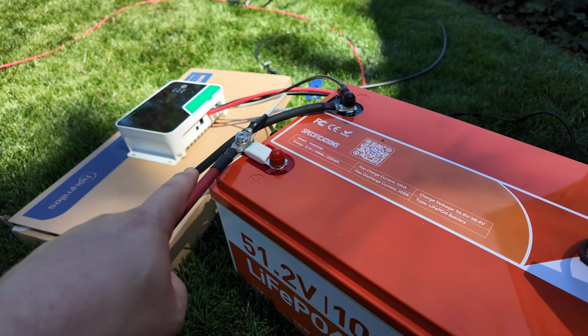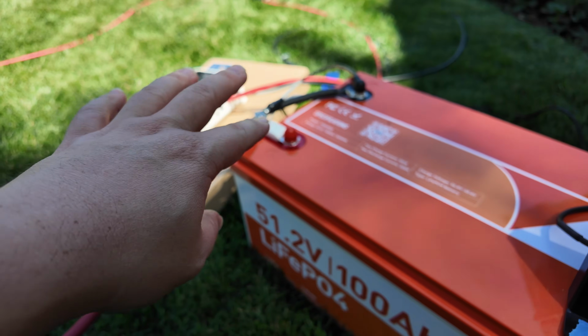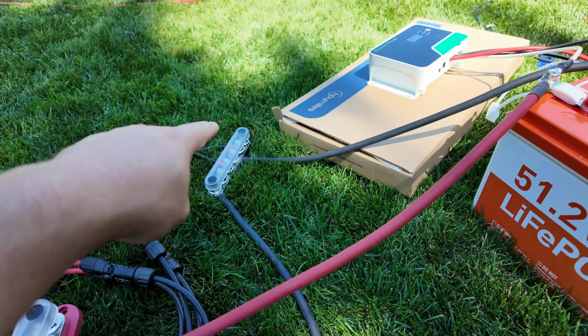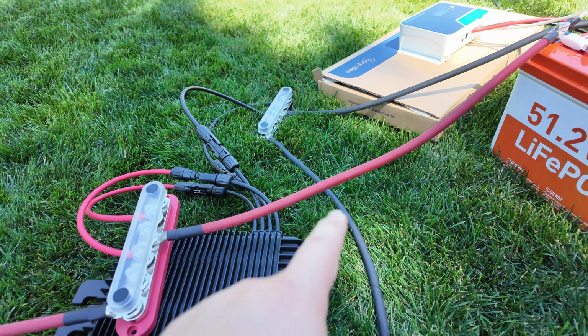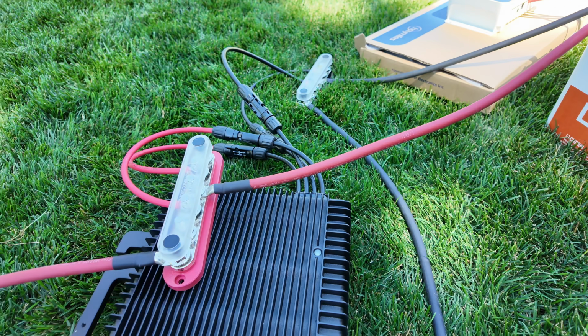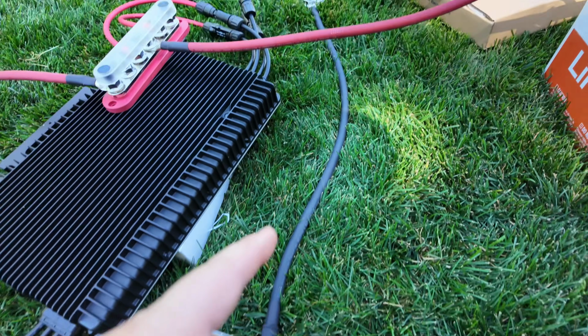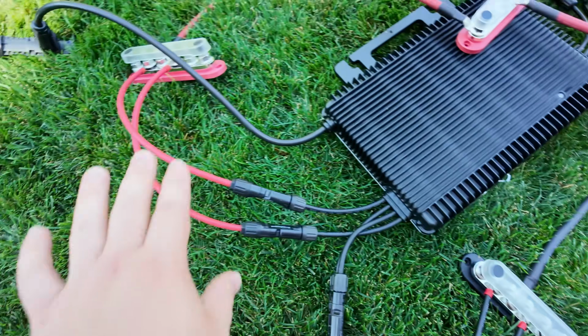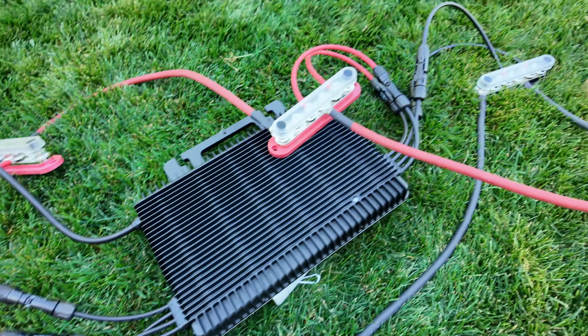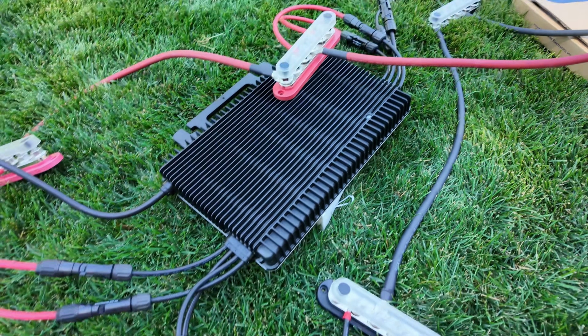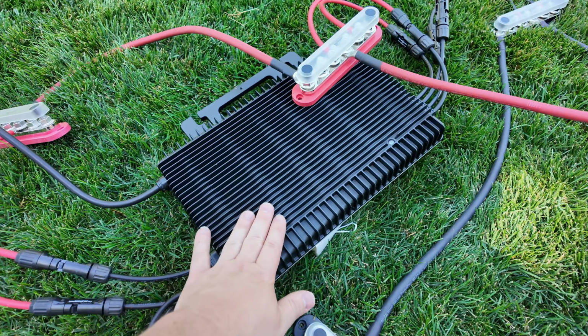I've got a fuse coming off the battery, positive and negative. The negative feeds one bus bar, and the positive comes over and feeds this bus bar. Then I've got another main cable going to 2 more bus bars for this side. These bus bars distribute DC power to the Hoymiles microinverter system.